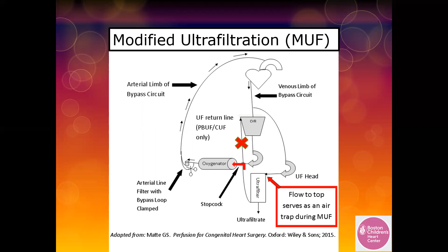Some important benefits of this technique include that if you are using an inline blood gas monitor, the hematocrit sensor is integral to the MUF circuit so that you can monitor hematocrit in real time. Another advantage is that there is no risk of drawing air across the oxygenator membrane. There is no risk of cerebral steal. There is no risk of coronary steal. There is no need for a separate heat exchanger. And there is no need for messing with the cardioplegia system. And the arterial line filter remains integral to the MUF circuit, which is something missing from traditional MUF techniques.